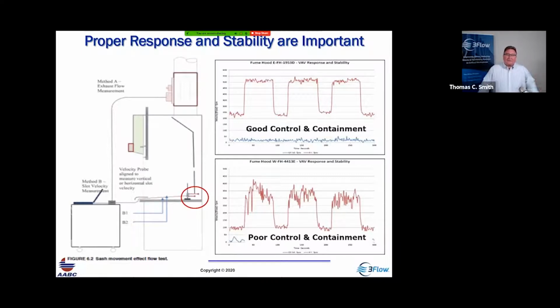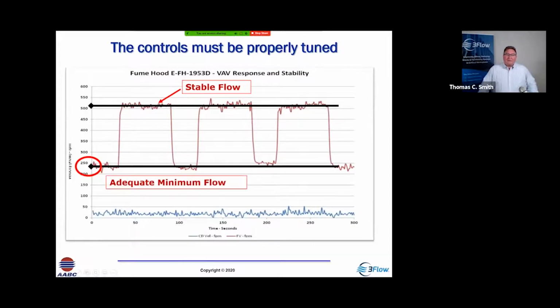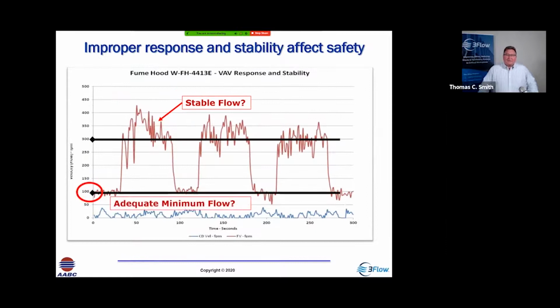Now you can imagine if the flow through the hood is varying, it's connected directly to the air supply. So what does the air supply have to do in order to keep it working in the proper balance? It's got to modulate as well. So these types of fluctuations are not conducive to hood containment, and they're not conducive to good VAV control. So something really important to look at is the operation of these VAV controls. Does it have adequate minimum flow? And is it stable? Those are the 2 questions we really want to know when we're testing the hood. If it's unstable or we don't have adequate minimum flow, those are going to cause problems, not only from the ability to conserve energy, but from a safety standpoint as well.